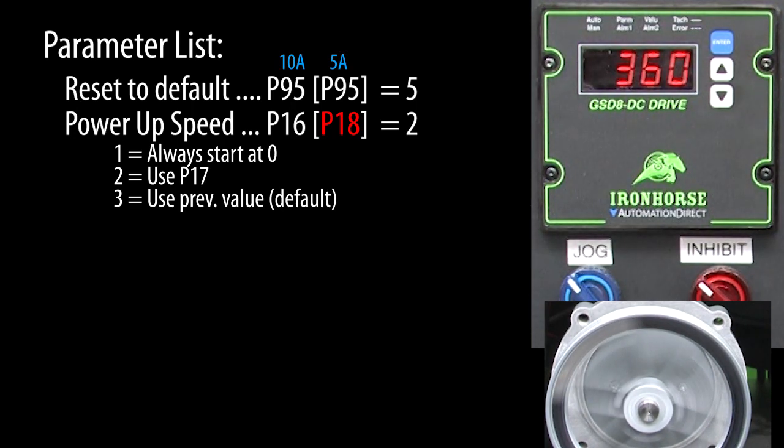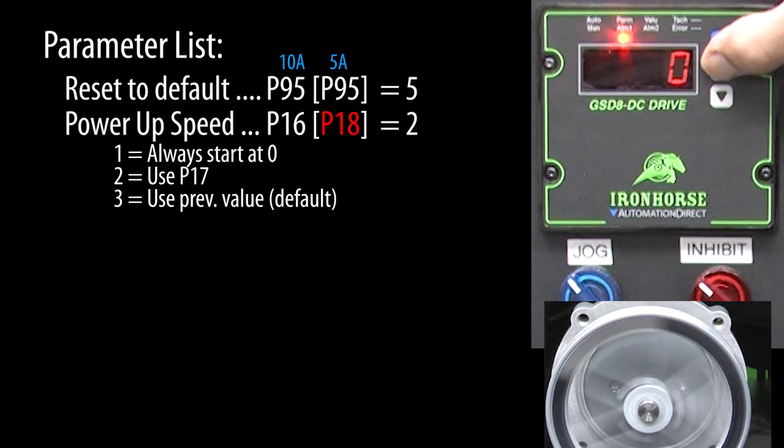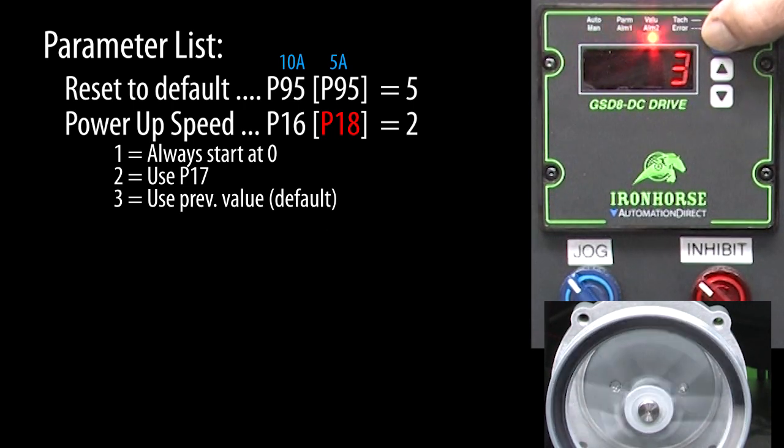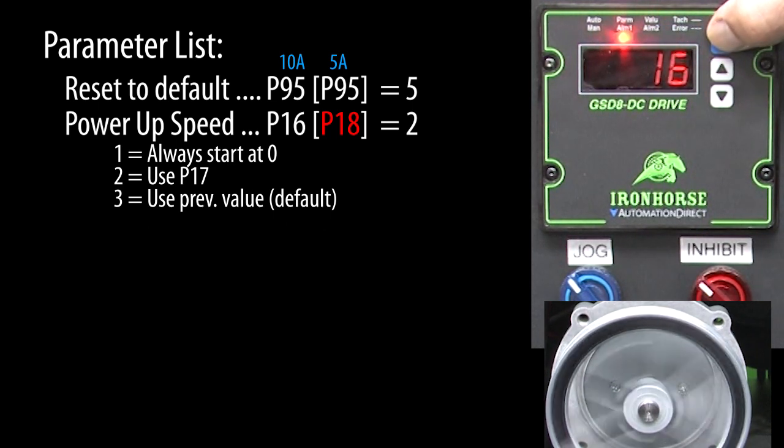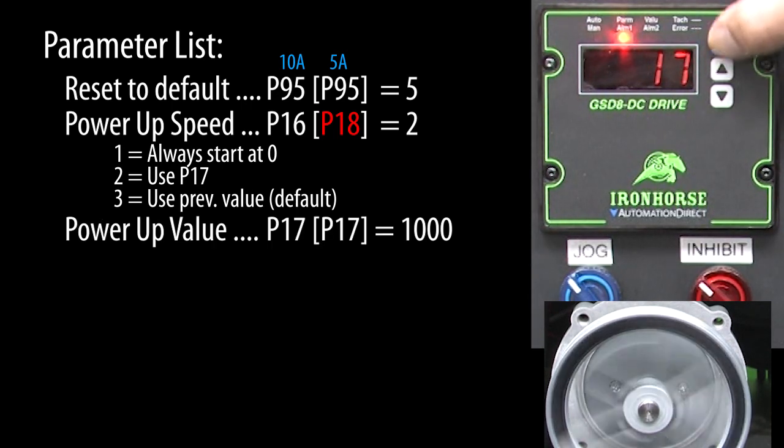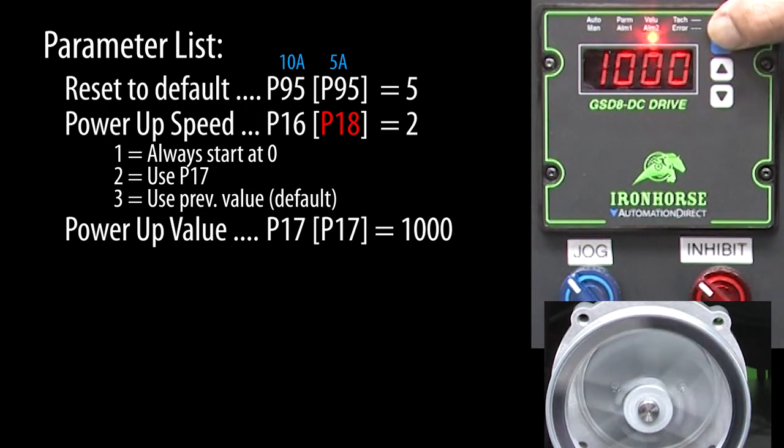Let's change that to use the value in parameter 17. I'll hold the enter button down for 3 seconds. The parameter LED lights up telling us we are in parameter mode. Scroll up to parameter 16, hit enter. Let's change it to use whatever we put in parameter 17, which according to the user manual is a 2. Enter to accept. Scroll up to 17, press enter, and let's have the drive always start at 1000 RPM. Enter to accept.